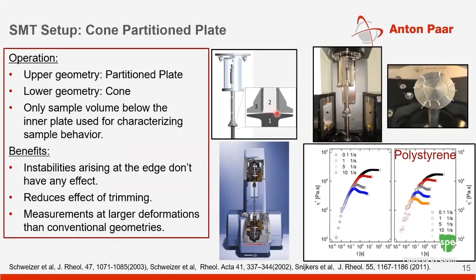And this has advantages, as you can see in the image on the right here. Even though edge fracture has happened, and as we saw earlier, the fracture propagates inwards, even though the fracture has started from the outside periphery, the sample inside where the measurement is happening is still intact. Hopefully this will be clear in the bottom data slide here, where the polystyrene data was generated on a traditional cone plate versus a cone partition plate. You can see how for steady startup shear experiments, almost a factor 10 increase in shear rate can be achieved just by using a cone partition plate. So that's another unique thing with a multi-drive device.